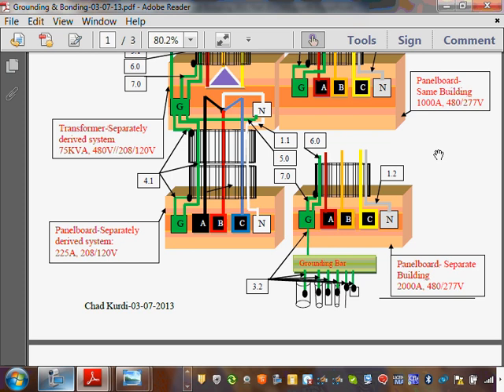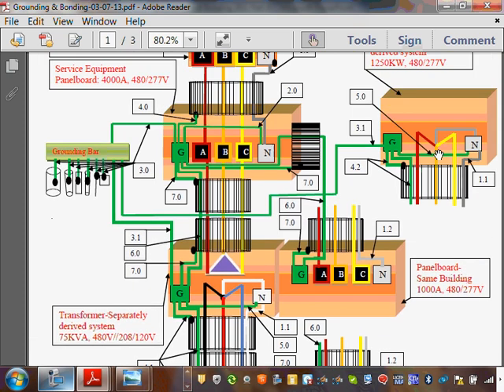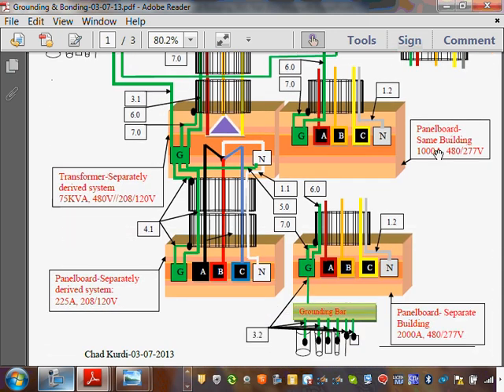Now, do you tie this to the top? Is that what you're saying? Yeah. Okay. Now this here to there, you don't have to, because they are tied through what? The equipment grounding conductor, right? Can you see that number 7 here? Let's go back. You see that 6.0 here? It's taking it from here all the way up and tying it. They are bonded together through the equipment grounding conductor. You don't have to. Does that make sense? They're already bonded through the equipment grounding. Did you encounter an inspector saying otherwise? I have a problem with everything.